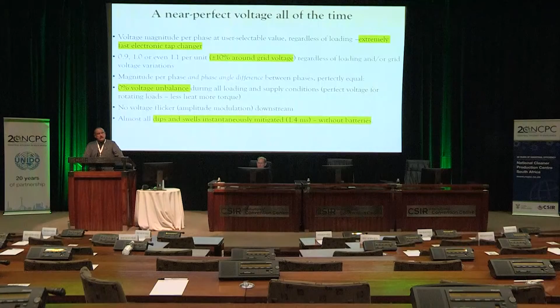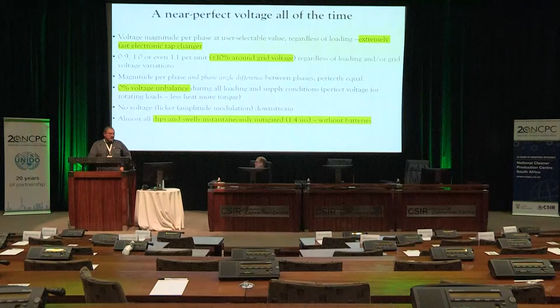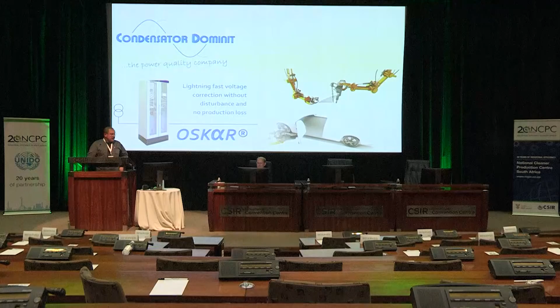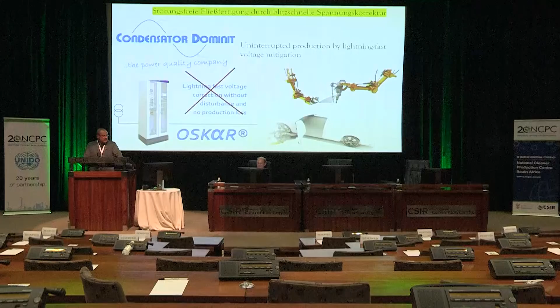We can do all of this nearly instantaneously, 1.4 milliseconds. Now consider a 50 hertz signal, 20 milliseconds each wavelength. So if you can fix up that voltage waveform in 1.4 milliseconds, the equipment will not know this, and that is done without batteries, without storage. So there is the typical solution, shown here already, the robotic arms. And I just have added there that on their description in the German, they didn't translate it very well, but it means literally that one can realize, and that is where business risk for a lot of the industry in Southern Africa sits, to realize uninterrupted production. That could be beautiful. And this is done by really fast voltage mitigation, which I will get to.